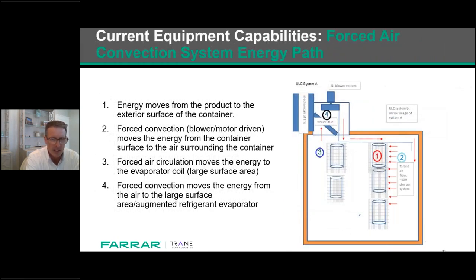Similar to the previous slide, once again, we evaluate the ability of the refrigeration system to eject the energy that it receives, again, from the second half. Now let's look at the mechanism. Again, this is the one issue that's often ignored. As you can see here, number one is still the same, where we have the energy moving from the product to the exterior. Number two is where it differs. We have forced air, which is the blower motor that moves the energy across the container. And then three, in the blue circle, this is where the circulation moves the energy to the evaporator coil, which is at the top. And then four is where we force the energy from the coil to the larger surface.